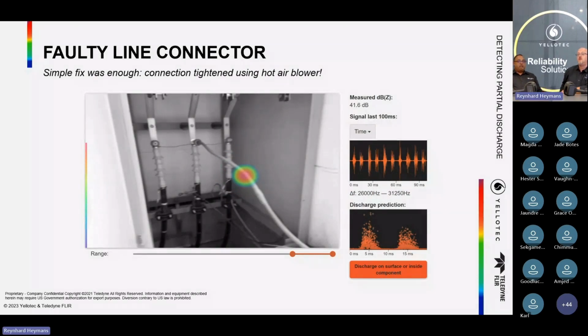Here we've got a faulty line, again, discharging through the insulation. Okay. This is the track that is coming through. And again, the AI tells you exactly what sort of problem this may be. So a bit of a description and a severity. Severity obviously being critically important. On that image, for example, it mentions from 26,000 hertz to 31,000 hertz. The AI automatically sets it up. So the AI on the camera actually picks up on that frequency band. So we're able to, again, take out all of the noise and we can pinpoint on that specific frequency band. And then it breaks it down into the discharge prediction and it gives a recommendation.